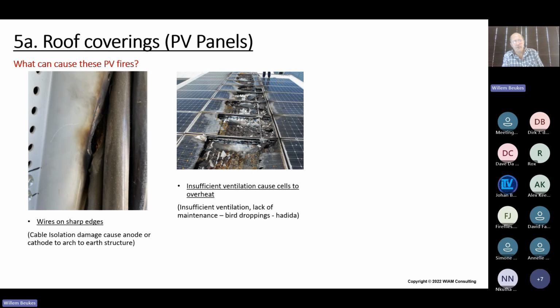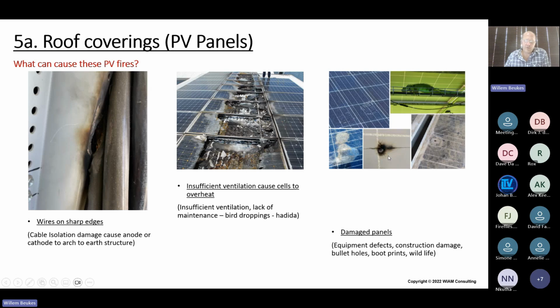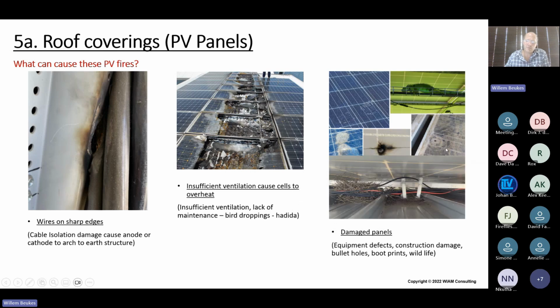And then also in a lot of situations, you have bird droppings or leaves that cover a cell, and then those cells overheat. I'll go a little bit later on in showing some videos on how this cell overheating happens. You have some other scenarios where the insulation of the panel gets damaged with installation, and then an arc forms at the back of the panel. You have dendrites that form between the anode and the cathode side of that panel, and then arc formation forms on the panel surface. You have cracked glass, you have bullets going through the panels here on the right. You have animals starting to live in this environment, birds making their nests underneath panels, and all of these contribute to a fire or to an arc forming scenario where these panels then start arcing and then start producing a DC fire on the roofs.